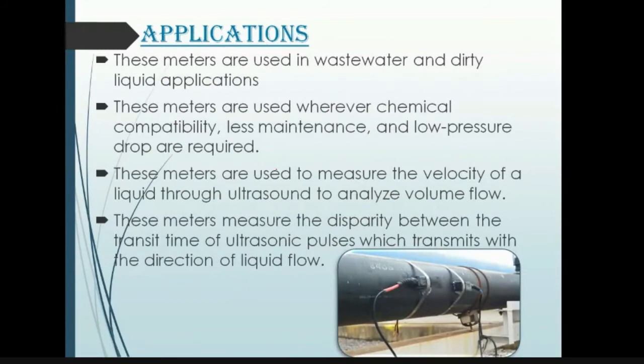These meters are used in wastewater and dirty liquid applications, and wherever chemical compatibility, less maintenance and low pressure drops are required. They are also used to measure the velocity of a liquid through ultrasound to analyze volume flow. These meters measure the disparity between the transit time of ultrasonic pulses transmitted with the direction of the liquid flow and against it. Now in this diagram we can see two devices called clamp-on meters.